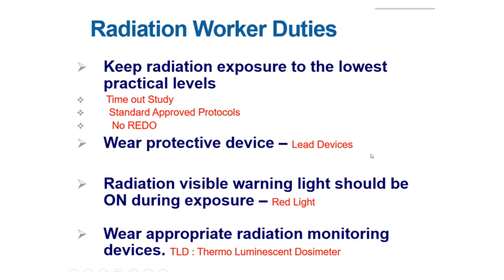TLD badge, that's thermoluminescent dosimeter. You should wear your TLD badge. The instructions for the TLD badge are very important. As I said, you should wear only your own badge, which should carry your institution number and your personal number. Always there is also a control badge, which will be stored in a radiation free area, which may be an ultrasound room or the radiology reception.